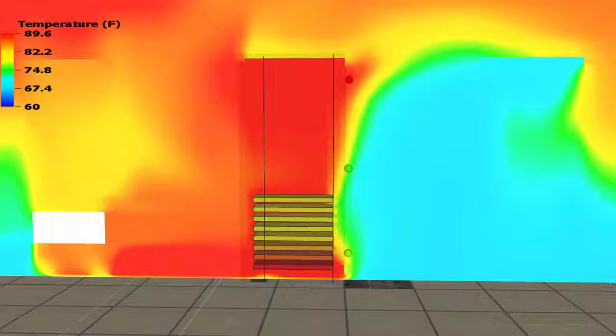So, to reiterate, cabinet sensor temperatures do not always correspond to the actual IT inlet temperatures. Internal mixing and recirculation can affect IT equipment temperatures without your sensors even telling you. In the end, monitoring does not ensure that your assets are safe.